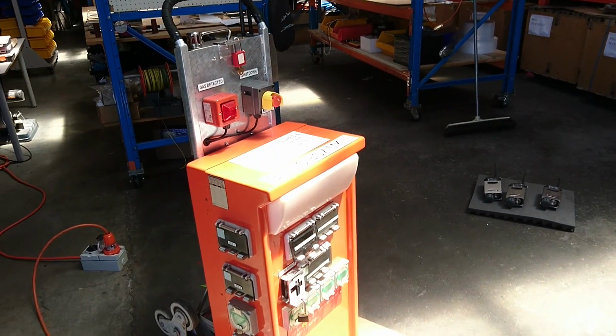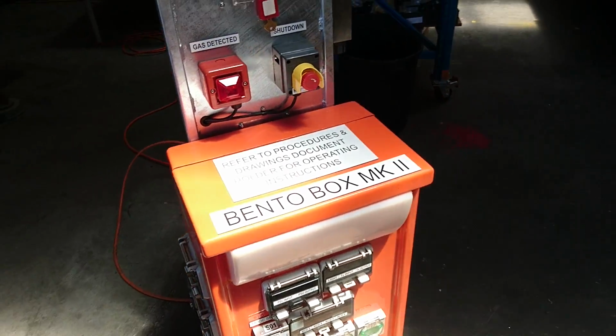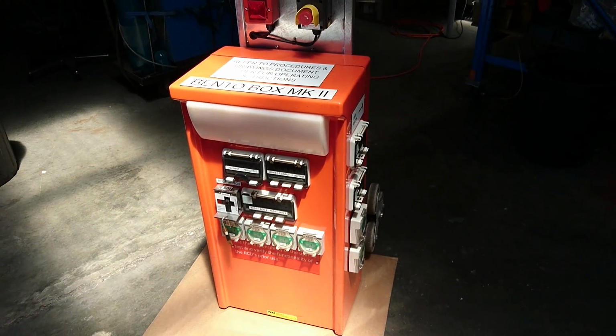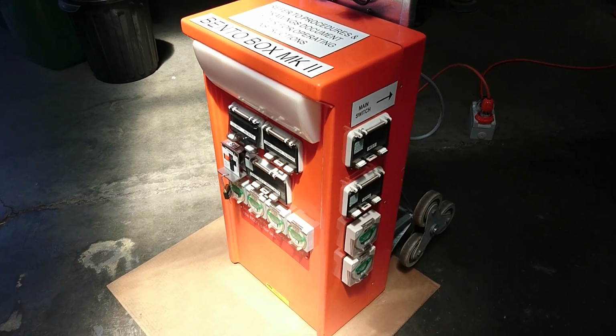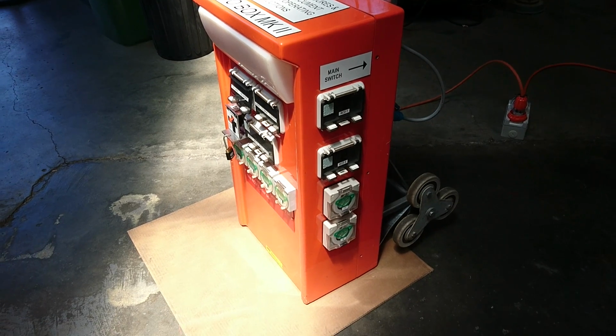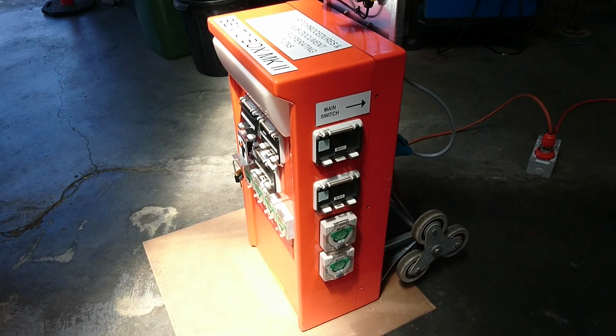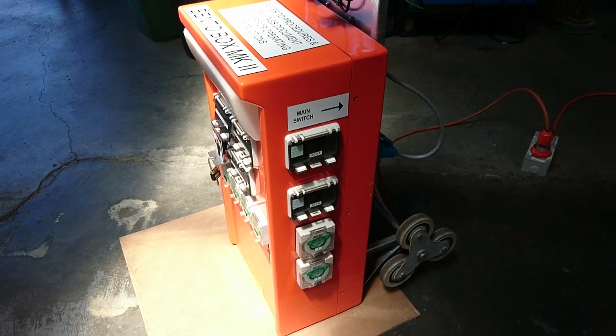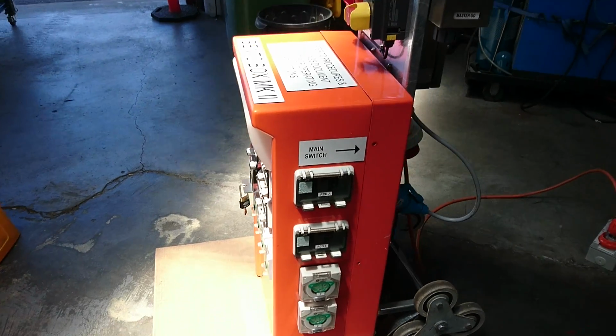Alright, so now I'm going to show you how to set up the bento box for gas detect mode. That's when you want the bento box to automatically shut down its power output when flammable gas is detected at a predefined percentage of LEL.